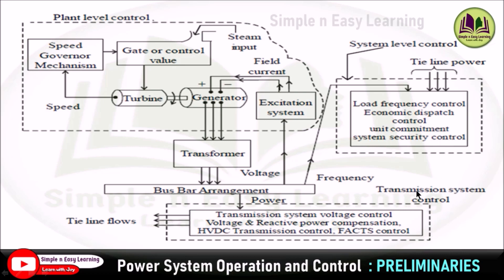Now we are going to talk about transmission system voltage control. In the transmission line, voltage changes occur due to the effect of transmission line parameters such as resistance, line inductance, and line capacitance. Transmission system voltage control is the process of controlling system voltage within permissible limits — for example, plus or minus 0.05 per unit or plus or minus 5%. The devices used to control transmission system voltage are capacitor banks, reactors, static VAR compensators (SVC), tap-changing transformers, synchronous condensers, and FACTS devices. The process of control is carried out automatically without affecting system performance, and reactive power is compensated using FACTS control to regulate the voltage.